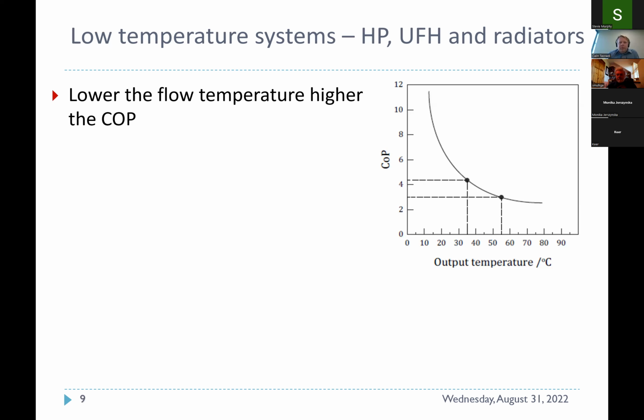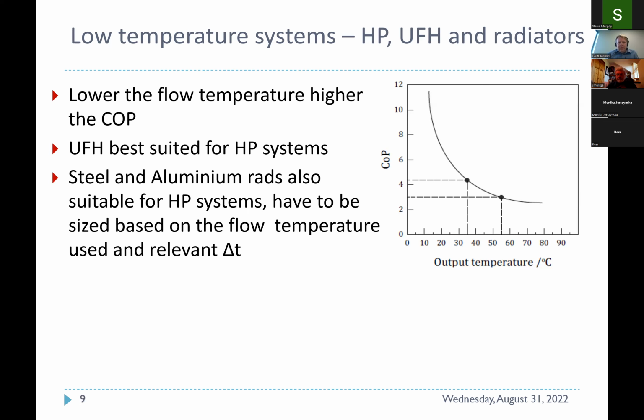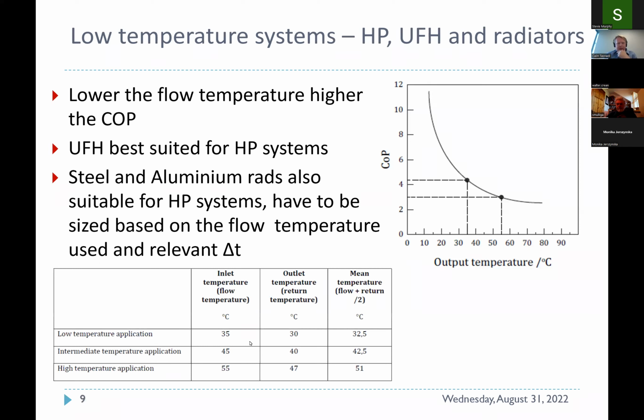Because of the high efficiency that we can achieve at lower temperatures, the best suited system for a heat pump is an underfloor heating system. Typically, in particular for developments, and not only, you also have steel and aluminum radiators that are being used with this. But we have to remember that they have to be designed for a lower flow temperature, typically around 40, 45 degrees, to ensure that we're getting the best efficiency that we can out of the system. Same table that I was showing earlier. Now, just to give us in this instance our mean temperatures.